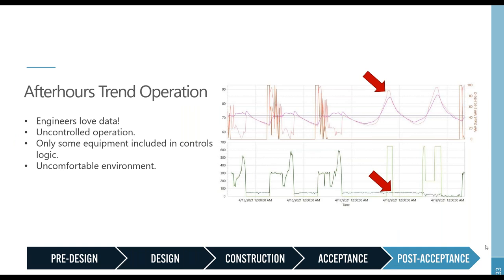So in this case, because of our trend review, we were able to quickly look through about a week's worth of data for every part of the building and see that one half was not included in this logic. So we were able to resolve that shortly after the building had been occupied. And that way we can now have a comfortable environment for that hardworking mayor who wants to be in there on a Saturday working away to try to make the city better.